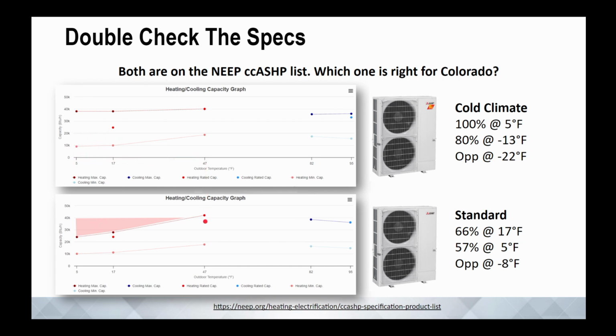So at 47 degrees, they look great. At 17 degrees, this lower one looks less great. That red wedge is resistance heat that you're going to have to make up. That's heat you have to fill in the gap with, and probably electric resistance, and probably more expensive. And as it drops down to 5 degrees and lower, that continues to slope down, eventually to the point where this lower system is going to turn off. It will shut off at -8. That's the cutout temperature on this particular piece.